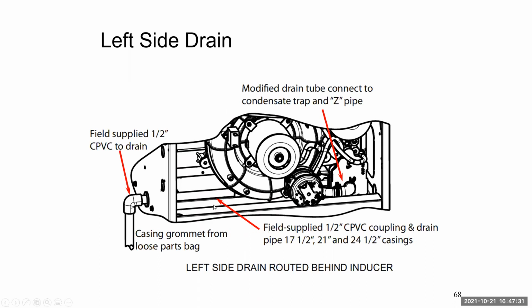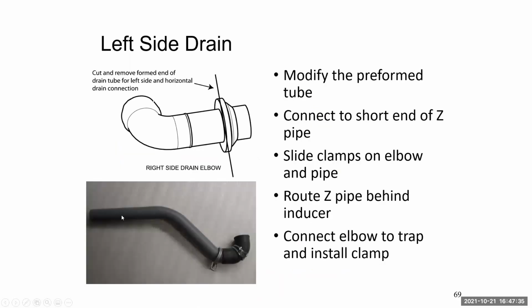If you are going to drain out the left side, I'm going to jump ahead 1 slide here. You have your Z pipe. That is what's used to exit the left side of your furnace. Make sure that that's laid flat across your furnace and does not have an uprise to it coming off that 90. And if you have an uprise in it, you're going to get water trappage.